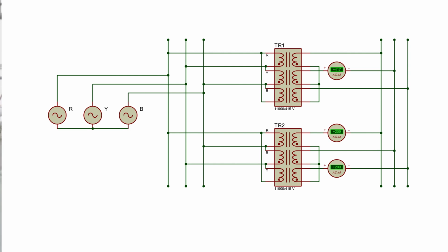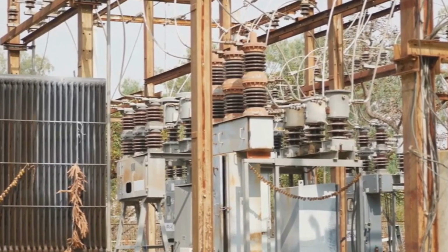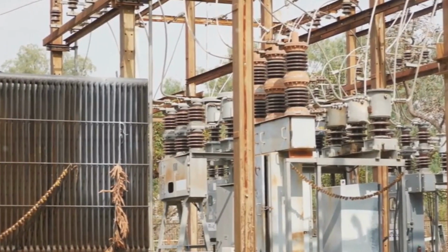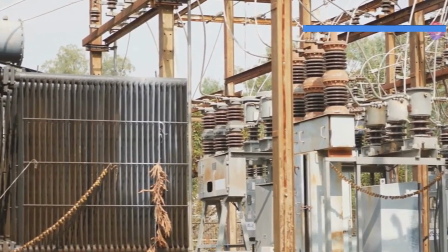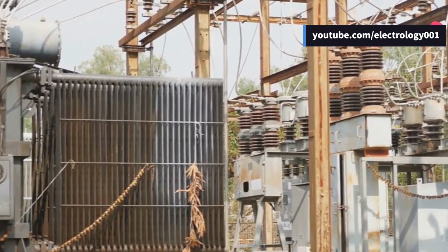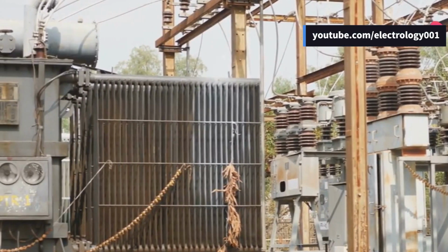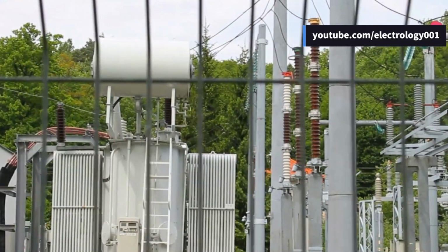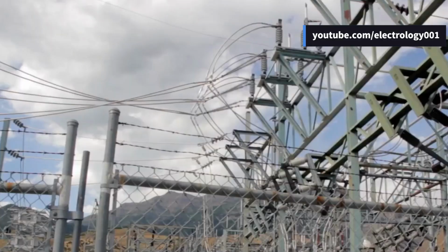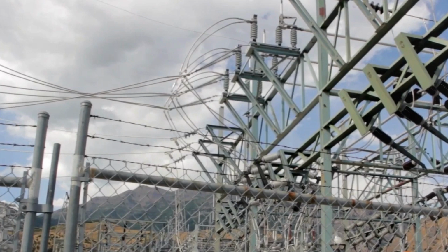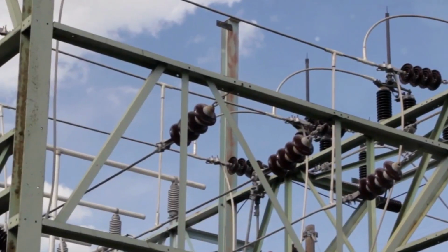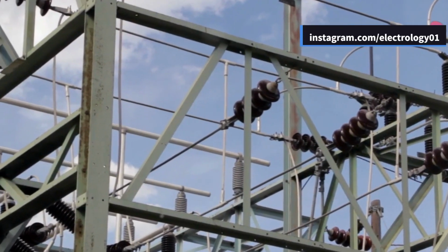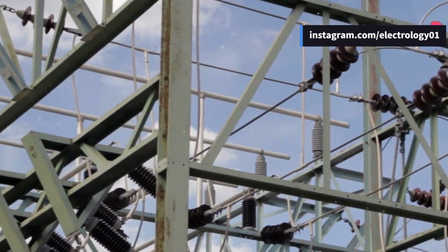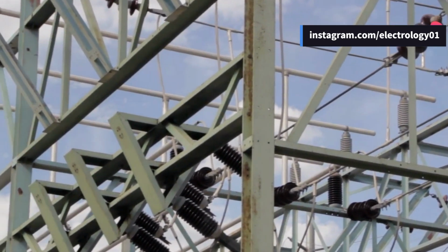close as possible. To sum up, for transformers to operate efficiently in parallel, they must have the same voltage ratio, percentage impedance, polarity, and phase sequence. By adhering to these conditions, power systems can avoid unnecessary losses and operate at their maximum efficiency. So, the next time you see transformers humming away, remember the precise conditions they need to meet to work together in harmony.